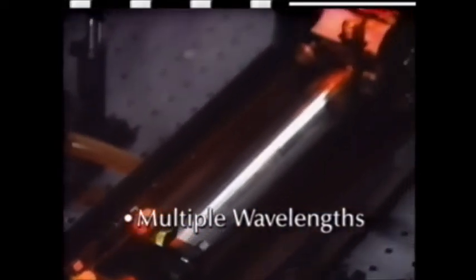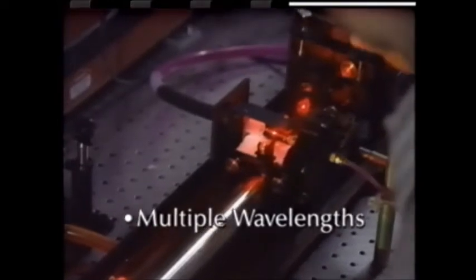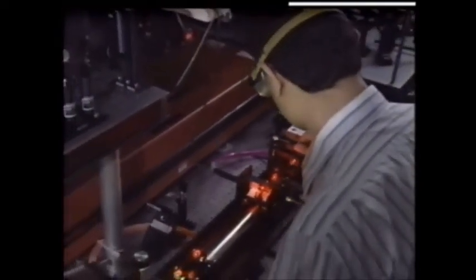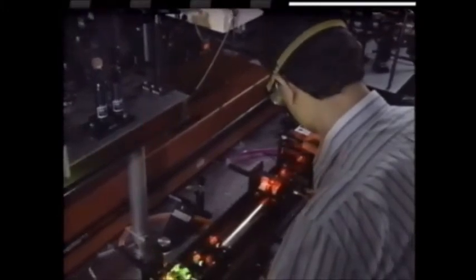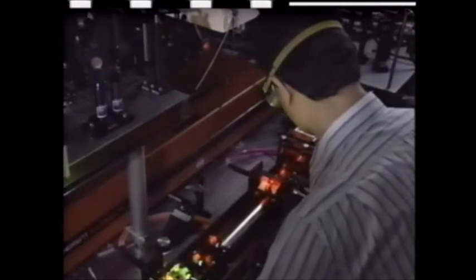A single laser can generate multiple wavelengths, some visible, others invisible. In addition, when a laser is used as the pump for another laser, there may also be more than one wavelength. A potentially hazardous error is to select eyewear that is suitable for only one of the wavelengths.